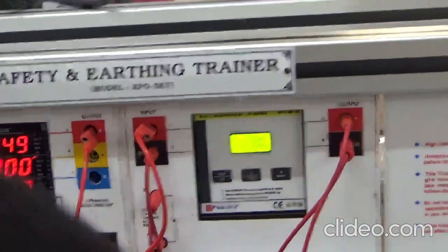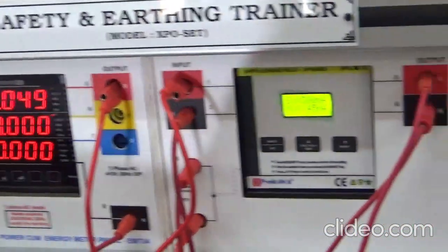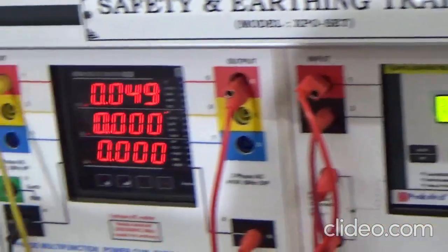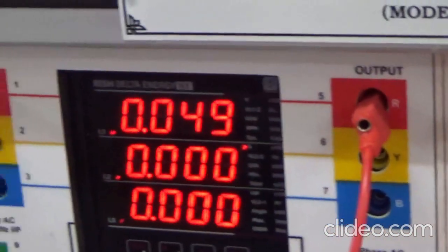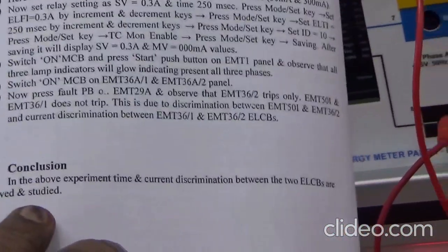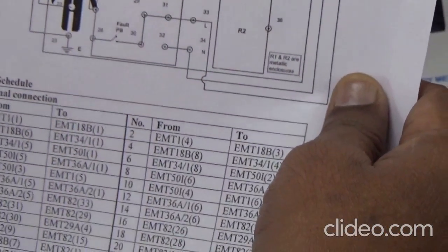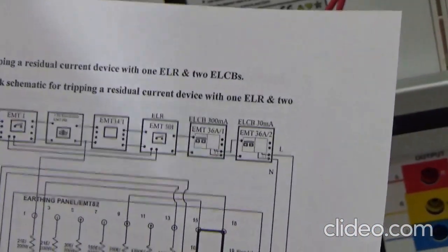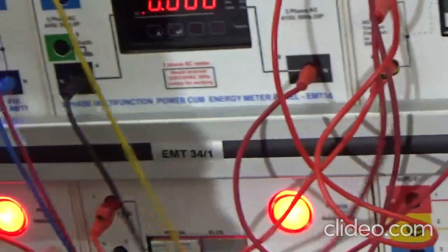Now I'll press this one. The current is right now 0.049, and only this one will trip. See, I'll press it. This one only has tripped, this is not tripped, and here also no tripping, nothing. So in this way, the conclusion is, in the above experiment, time and current discrimination between two ELCBs are observed and studied. So in this way, I have completed tripping a residual current device with one ELR and two ELCBs. The two ELCBs are here.